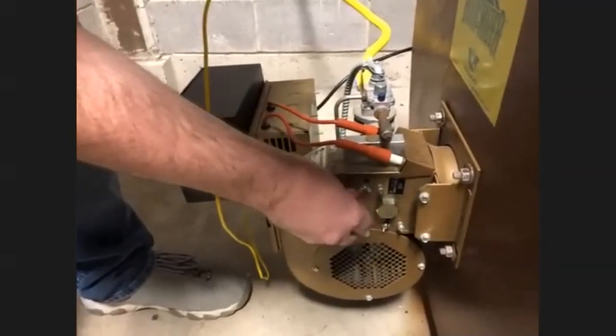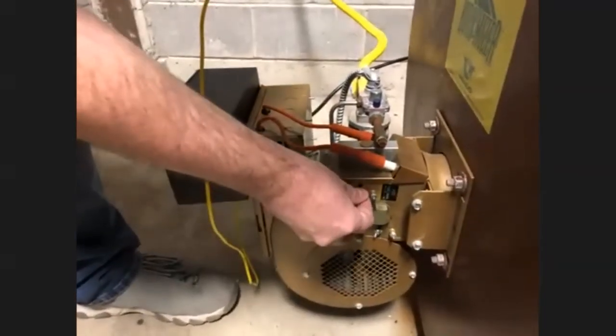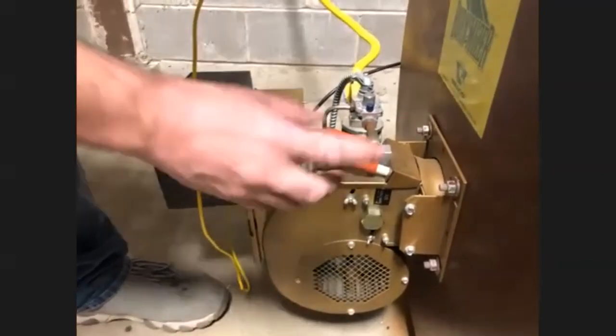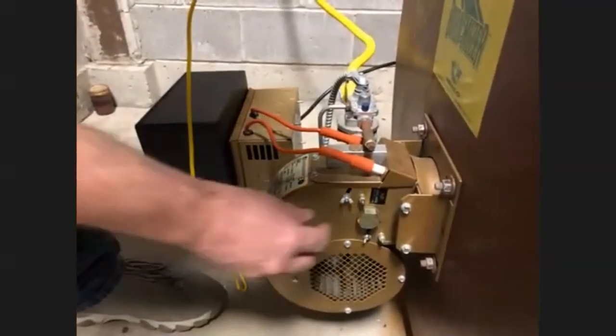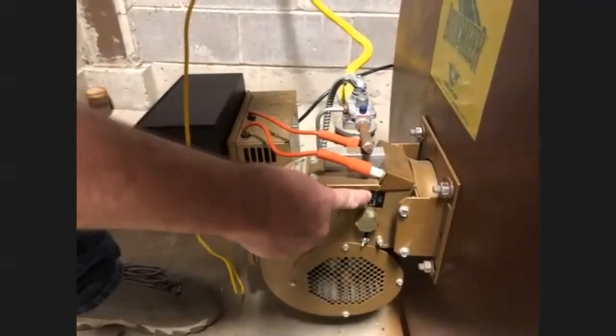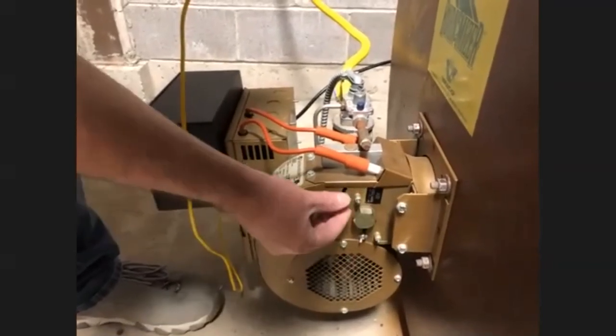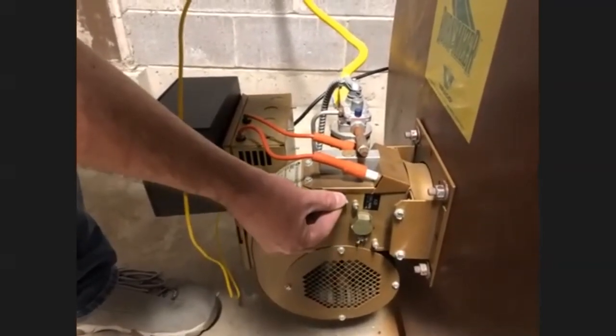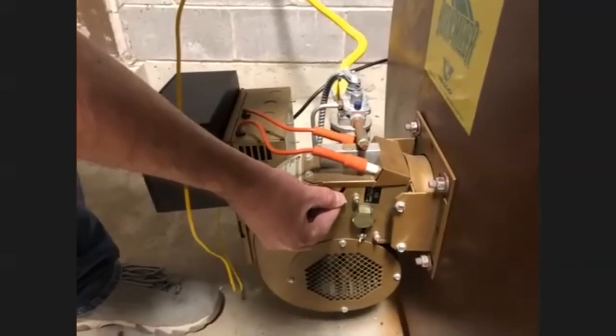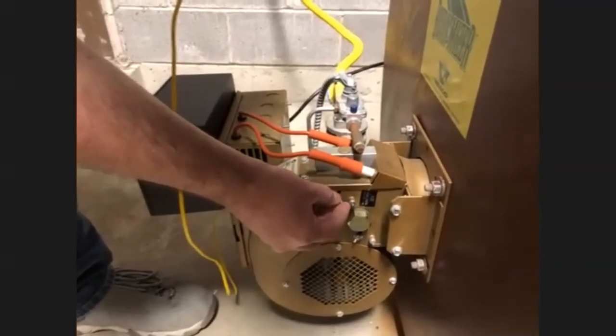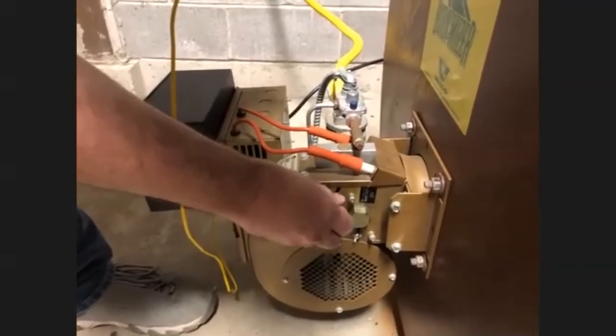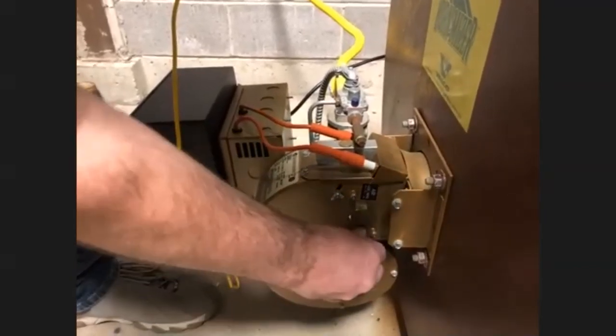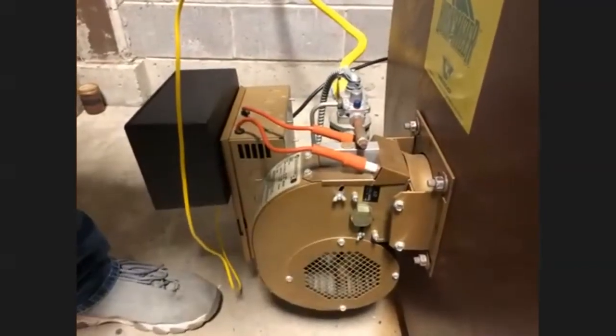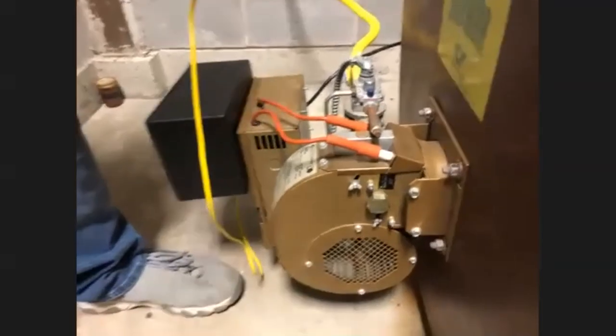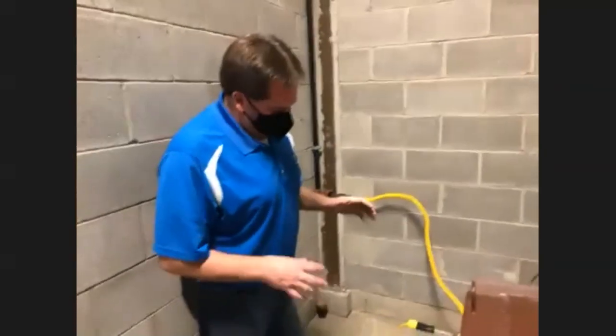And what you're doing on a gas burner, you want the maximum amount of air with no black smoke coming out of your exhaust. You can see right here, this decal and its adjustment: you have less air if you rotate this up and more air if you bring this down. So you always want these set for the maximum amount of air, tighten those down, with no black smoke coming out of the stack. And that'll give you your proper efficient burn rate.